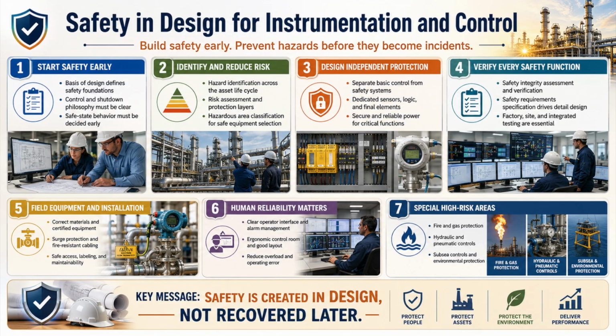Fire and gas detection provides another independent layer. It acts after loss of containment and must detect the event early enough to isolate, shut down, depressurize, ventilate, alarm, or initiate other protective actions. Detector type, location, coverage, obstruction, environmental conditions, false alarm sources, maintenance access, and voting logic all matter. A detector installed in the wrong place is not protection.